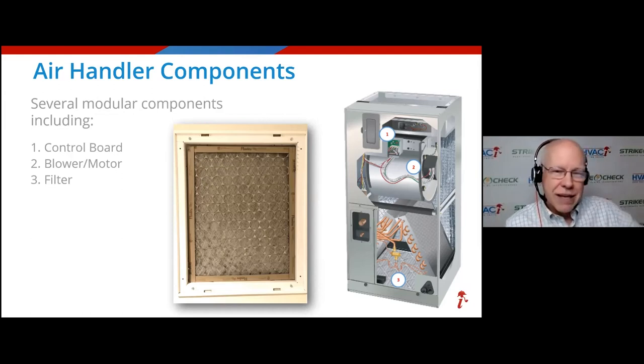Now, I would say in some cases they do, in certain hospitals, where they have to worry about IAQ, indoor air quality. But also a lot of people now, and this is anecdotally, since COVID, people are like, man, I want to filter the air in my home more. So they go out and they buy HEPA filters and they try to put them in their HVAC system. Be careful. These systems are not designed to operate with HEPA filters. Those are very tight. The blower and the compressor, you might burn them up because they can't pull enough air through those. They're not designed for that. These are just designed to get the bigger particles, and this is why.